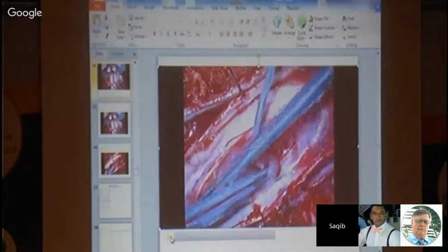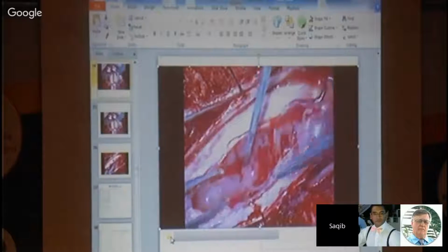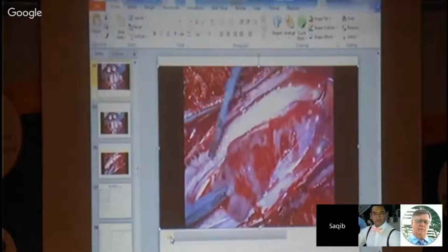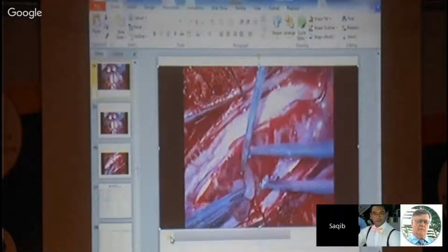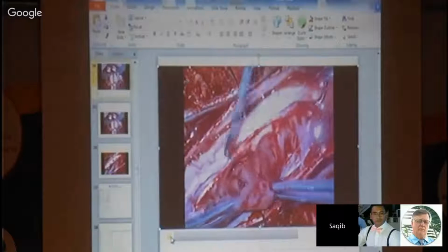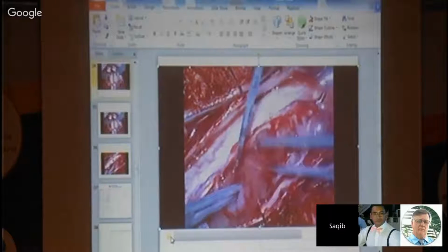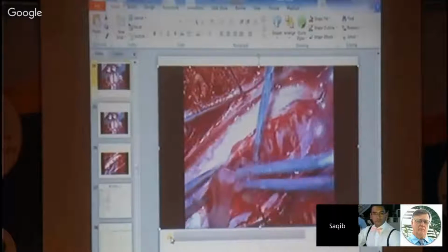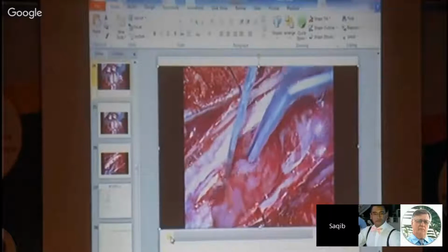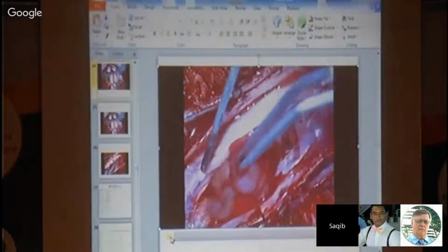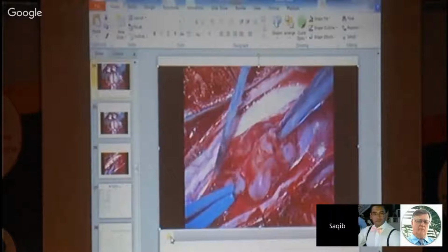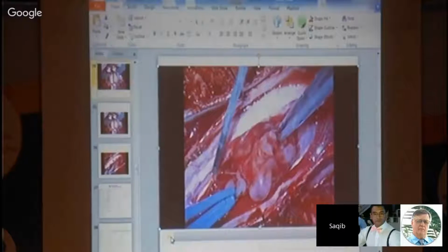They got another neurophysiologist, and another intramedullary spinal cord tumor case came up. They did the same stimulation, spinal cord mapping. That patient also had severe ventricular fibrillation and whatever else, and they were like, what's going on? So what I'm trying to tell you is, there are technical parameters that are important. When they checked the machine, this patient was stimulated at a 500 microsecond pulse. What I'm talking to you about is a 50 to 100 microsecond pulse. That was a bigger duration of pulse. So the current spread can happen, and it can go to the heart and all those areas. That's why technical parameters are important.